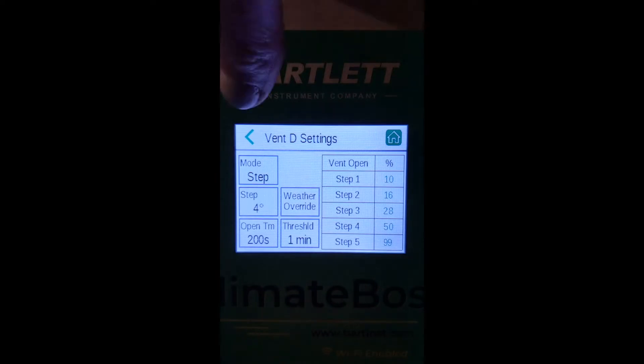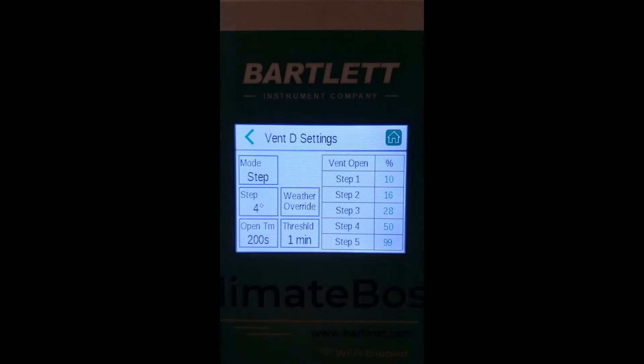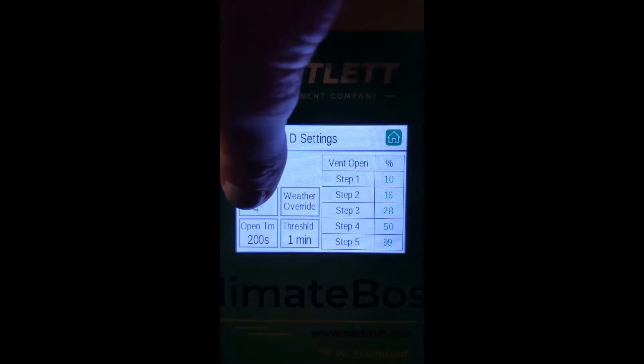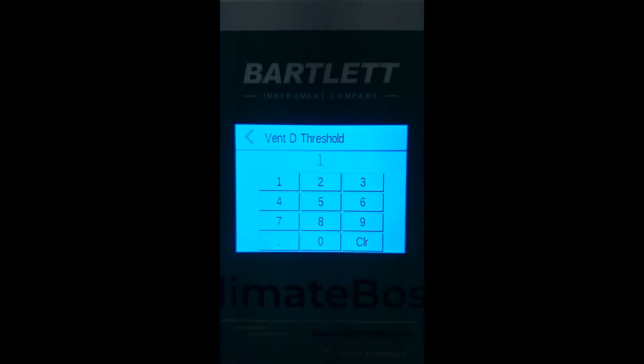On the vent settings page, you can see the mode, step open time, weather override, threshold time, and the step open percentage table. For any of the modes, you should first program the open time and the threshold time. The open time is the total time it takes for that vent to open completely. Currently, vent D is configured to have an open time of 200 seconds. The threshold time, configured in minutes, is the time the vent will wait for the temperature to regulate before it will change to another open percentage. For example, if the temperature is warm enough to open to step one, it will open and then wait one minute before it decides if it should open further to step two.